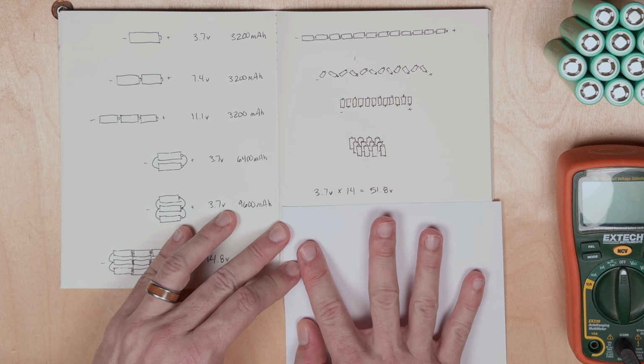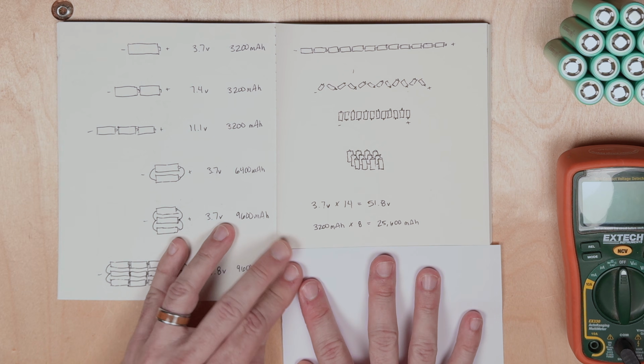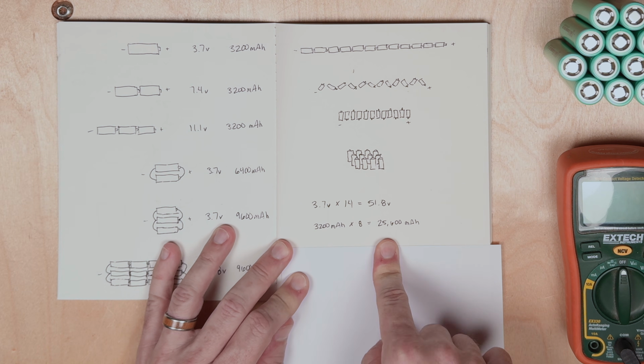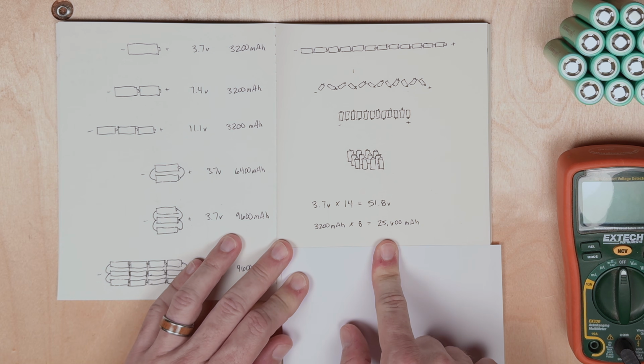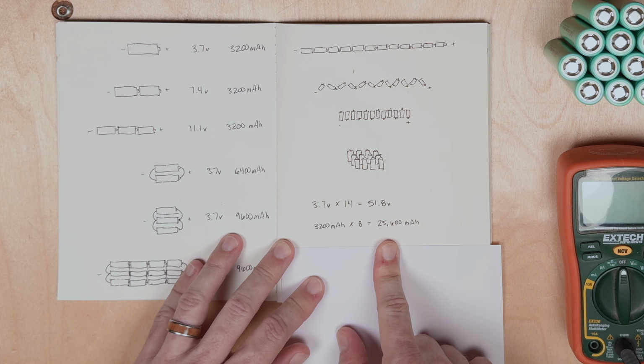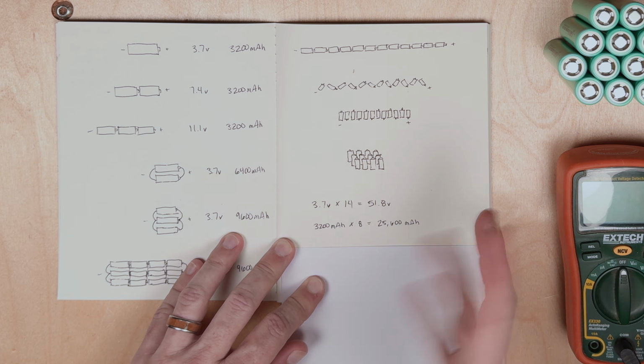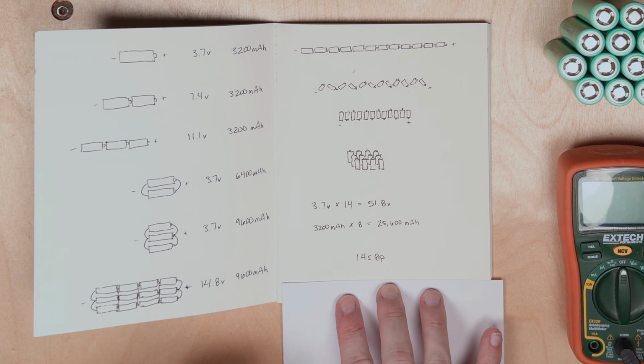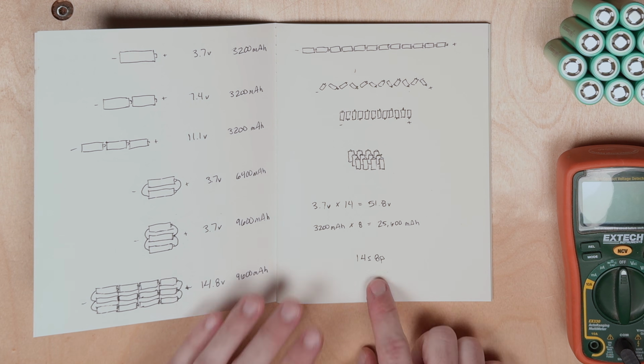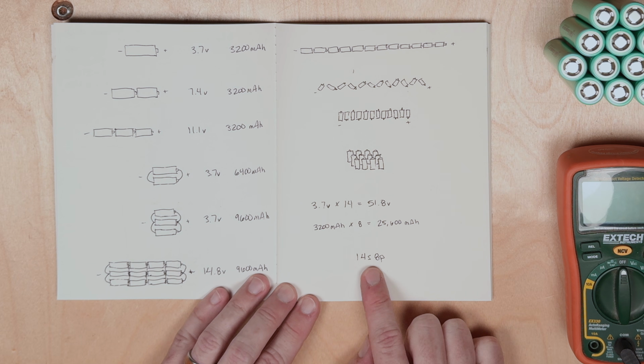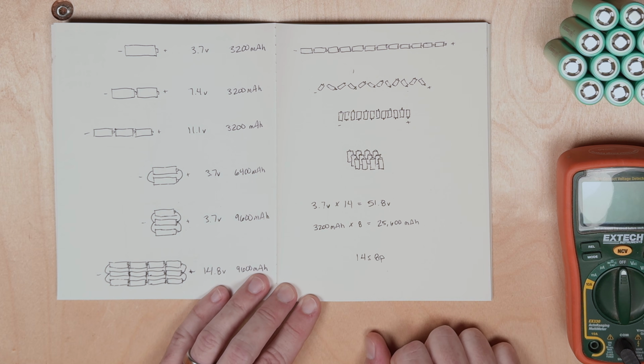And then to get to the capacity we need, we're going to need 8 of these. So 3,200 milliamp hours times 8 gets us 25,600 milliamp hours. You'll see this series versus parallel count referred to like this: in this case, I'm building a 14S 8P battery -- 14 in series, 8 in parallel. If you multiply those two numbers together, you get 112, so we'll need 112 of these cells to build this battery.